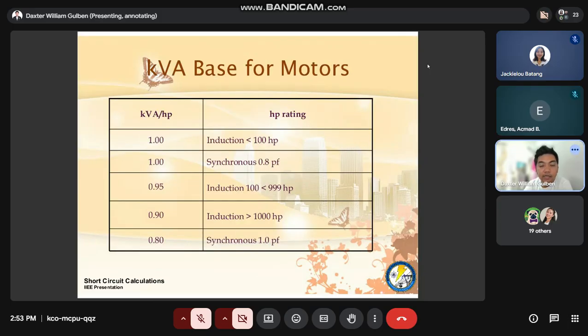And then in other cases, for particularly sa mga motors, natay gina-follow nga ratings per unit value, no? For example sa induction less than 100 horsepower, we have to use 1 kVA per HP equivalent. For a synchronous motor, we have 0.8 power factor, we have to use 1 kVA per HP. And induction of 100 to 999 HP, it's 0.95. Kini siya nakabase ni siya sa ato ang sa spec man siguro ni nga mga values.